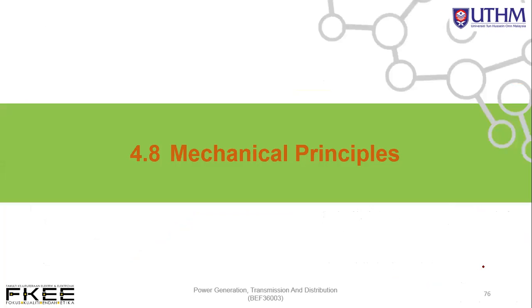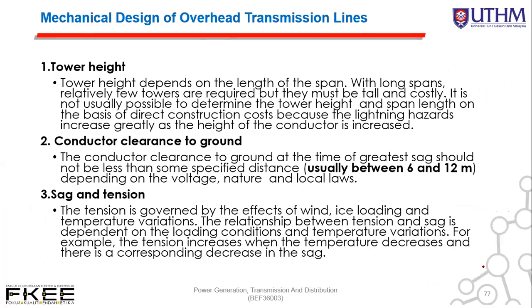Now we look at the mechanical principles of overhead lines. Mechanical design of overhead transmission lines must consider, number one, tower height. Tower height depends on the length of the span. The longer the span, the higher the tower height. With long spans, relatively few towers are required, but they must be tall and costly. It is not usually possible to determine the tower height and span lengths on the basis of direct construction costs, because the lightning hazard increases greatly as the height of the conductor is increased. Longer span means taller tower, so the lightning hazard will also increase.